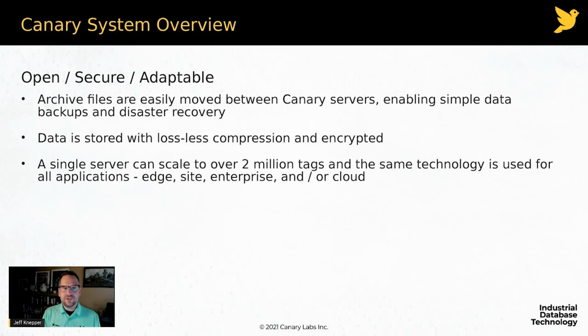So if a Canary server is licensed to have 1,000 tags, and you've got 500 tags over here in this HDB file, and you want to move it over to another historian, as long as the licensing is available for those extra 500 tags on the second historian, not a problem. There's nothing that would keep you from that, other than your physical security best practices, of course, accessing the archive itself or the machine itself. There's nothing that would stop you from our side from taking those HDB files and moving them to another server.